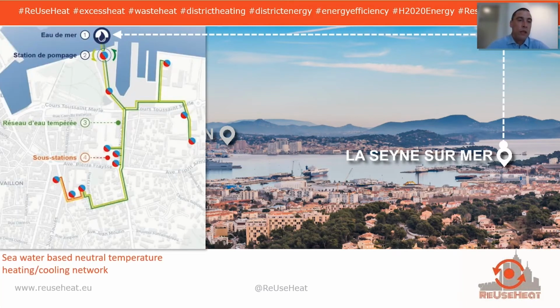In this network, as you see in the scheme, we have the seawater intake, done at 4 meter depth just beneath the shore, which exchanges directly at the pumping station. We have the exchange between the seawater network, driven by salty water, and the primary network, which distributes water to all customers using fresh water, so we have no problems of corrosion or other issues with the piping. So at the pumping station it's just an exchange station, as you might call it: we just find pumps for both networks and plate exchangers for exchanging the calories without any exchange of the water itself.